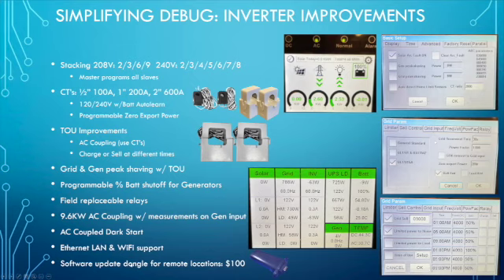We've always been able to do dark start with DC coupled panels. So if the inverter shuts down, even if the battery goes completely dead or the BMS shuts off on the lithium, when the sun comes back up it fires up the computers, starts the MPPTs, and starts charging the battery back up until it can turn on the AC output, the inverter output.